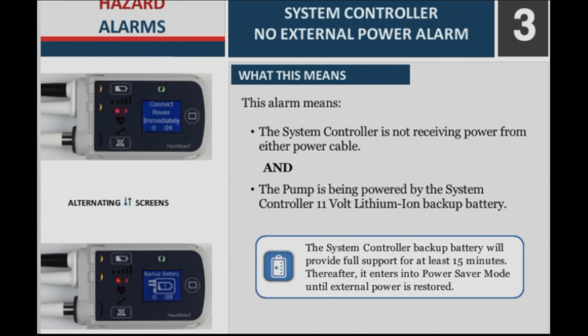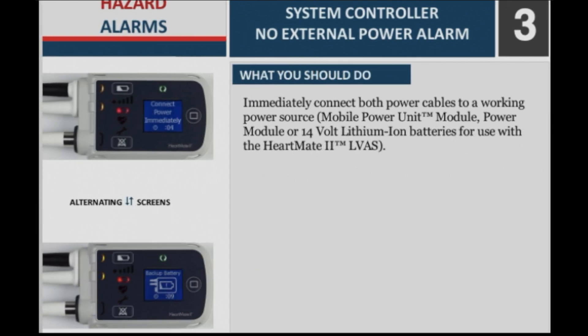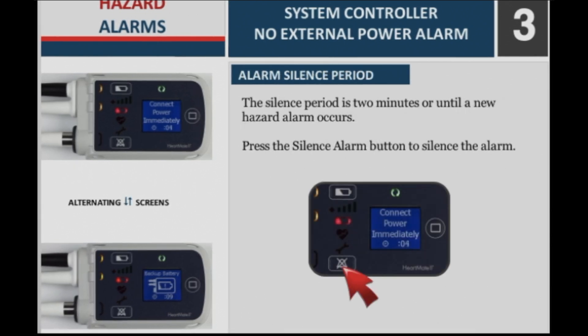The system controller backup battery will provide full support for at least 15 minutes. Thereafter, it enters into power saver mode until external power is restored. What you should do: Immediately connect both power cables to a working power source — mobile power unit module, power module, or 14V lithium ion batteries for use with the HeartMate II LVAD. The alarm silence period is 2 minutes or until a new hazard alarm occurs. Press the silence alarm button to silence the alarm.